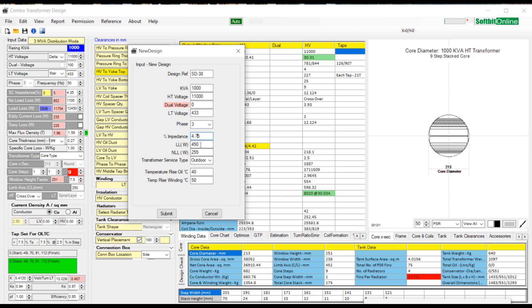Select transformer service type as outdoor type, temperature rise oil 40 degrees C, and finally temperature rise winding as 50 degrees Celsius.